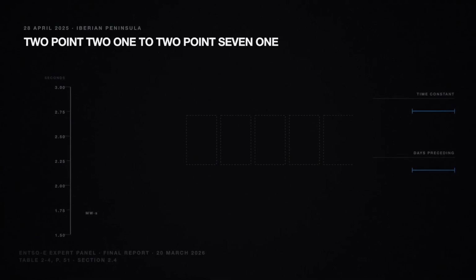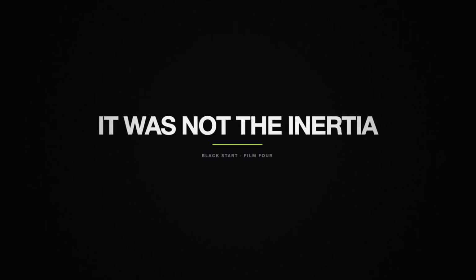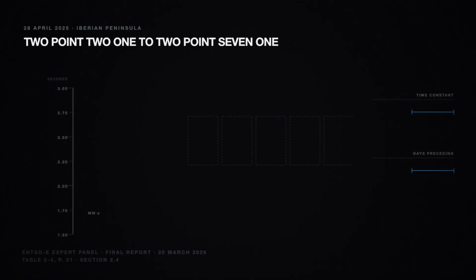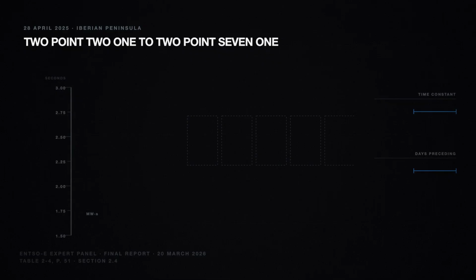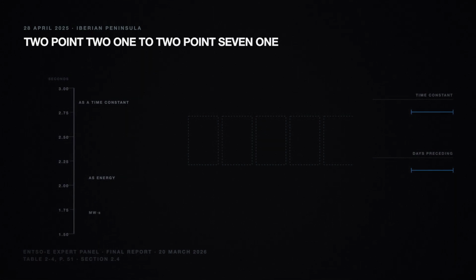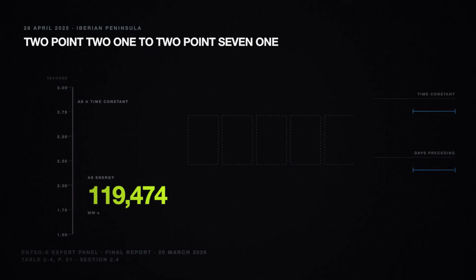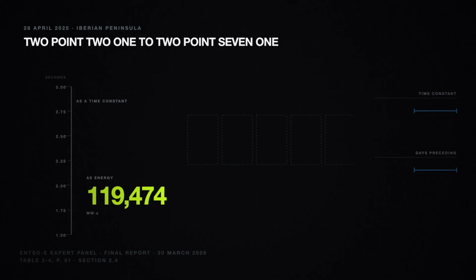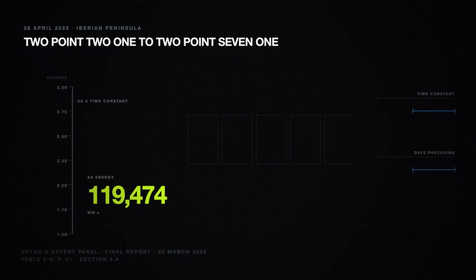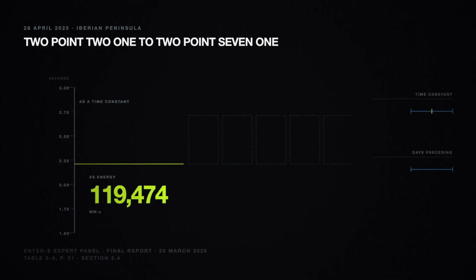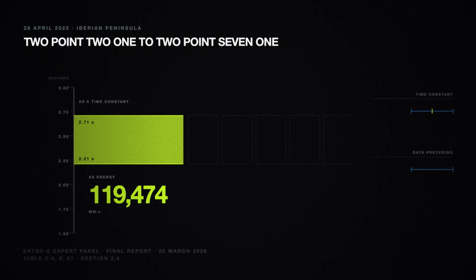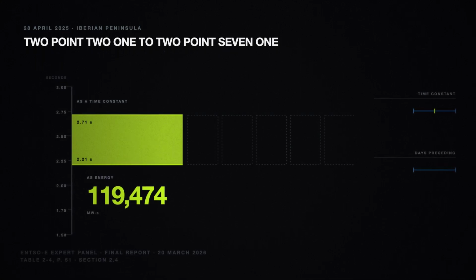Page 51 of the expert panel's final report carries a table numbered 2-4. It is the only place in 472 pages where the inertia of the Iberian Peninsula is given a number. Inertia here is a measure of stored rotational energy. The table gives it two ways. As energy, 119,474 megawatt seconds for the Iberian Peninsula on the day of the incident. As a time constant, it is not a value at all. It is a range, 2.21 to 2.71 seconds.